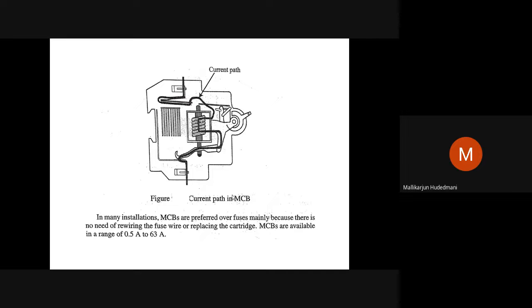Then reusability is considered. Fuse wire cannot be reused once it breaks down. We have to rewire it separately with a new one. But the MCB, it is reset. We say it has tripped off. The thermal metal strip has made its deformation. Once it cools down, it comes and engages the contact again. So this is called reusability of the MCB.